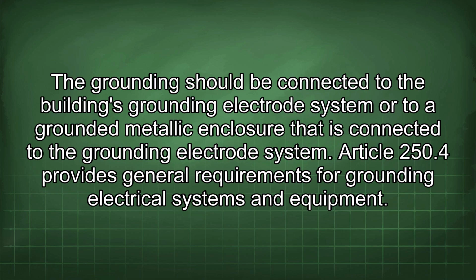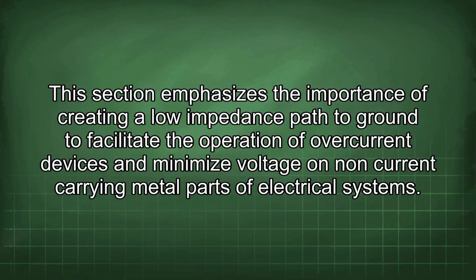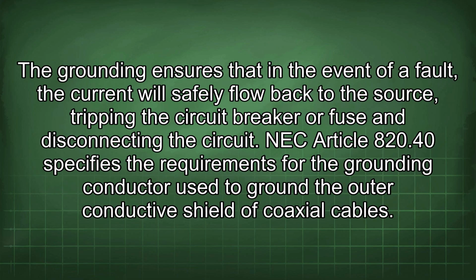Article 250.4 provides general requirements for grounding electrical systems and equipment. This section emphasizes the importance of creating a low-impedance path to ground to facilitate the operation of overcurrent devices and minimize voltage on non-current carrying metal parts of electrical systems. The grounding ensures that in the event of a fault, the current will safely flow back to the source, tripping the circuit breaker or fuse and disconnecting the circuit.